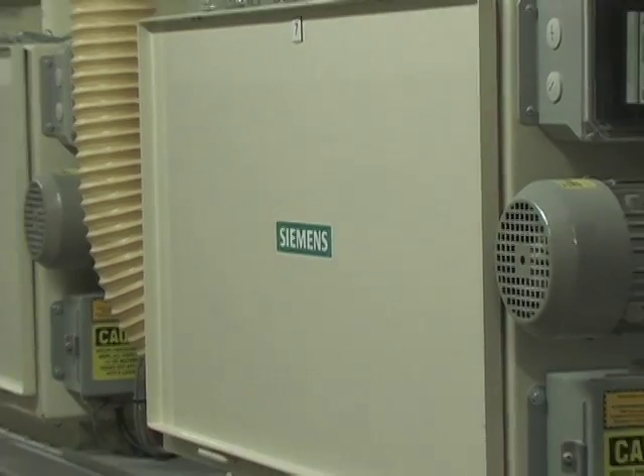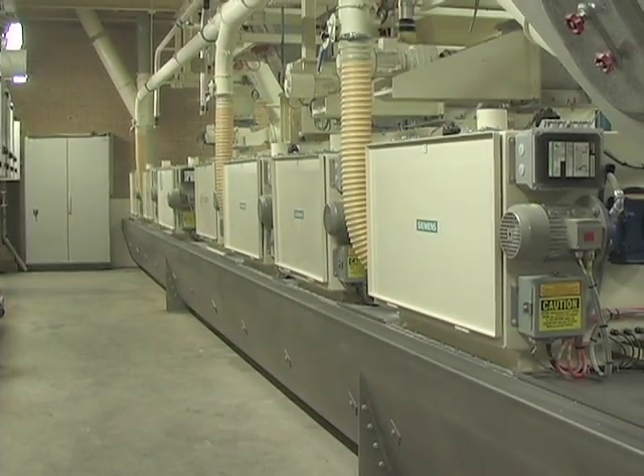The weigh feeders blend and batch 14 different products at the same time. They weigh the batches with an accuracy of 0.5% or better. The speed of the belt and the belt loading determine the correct dosage.